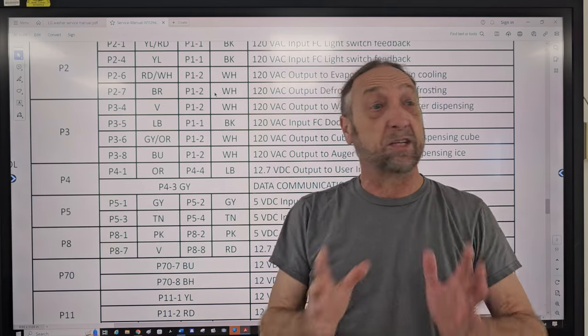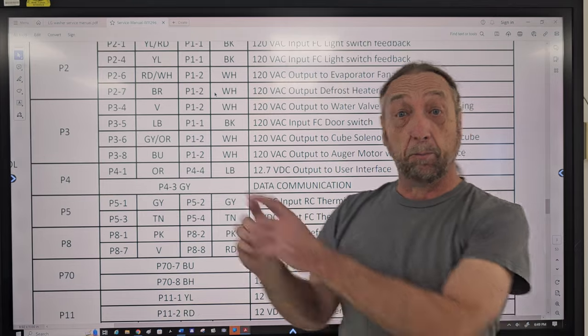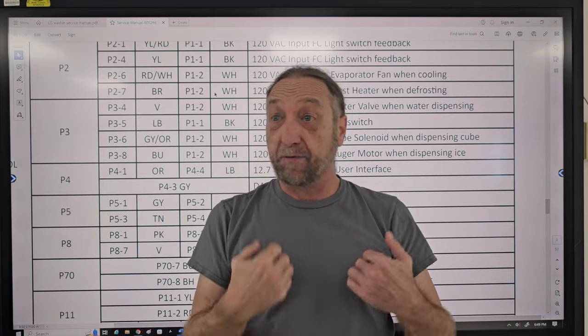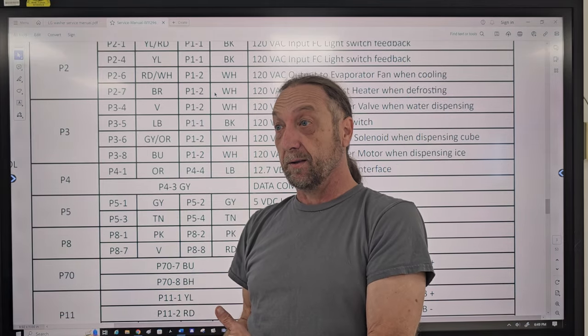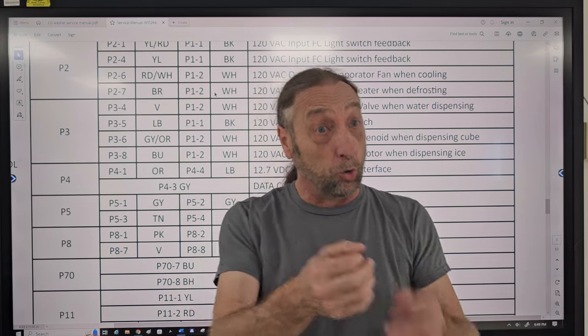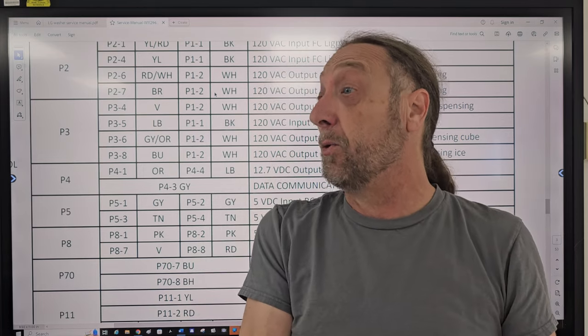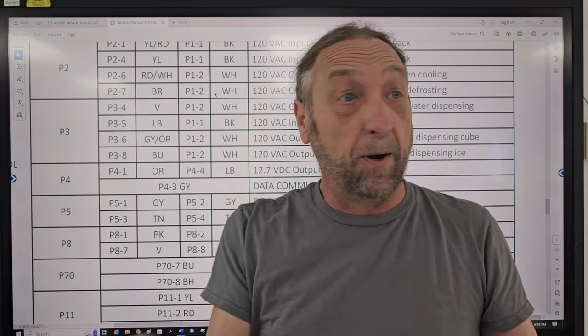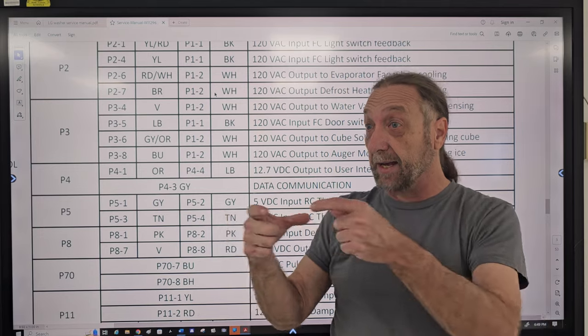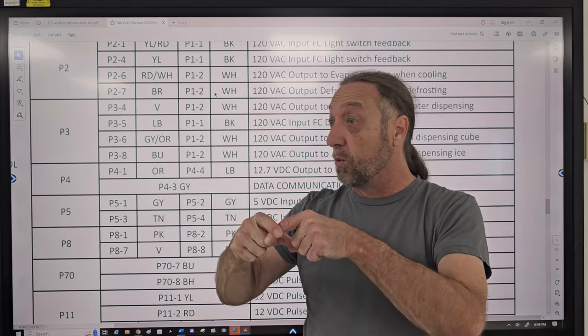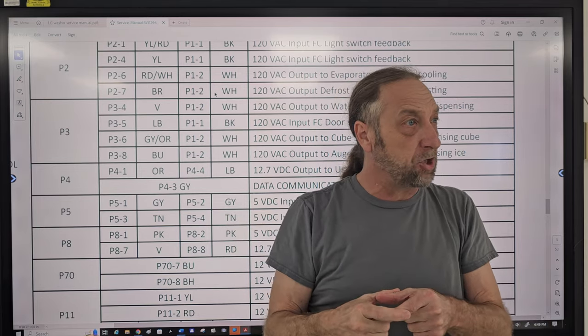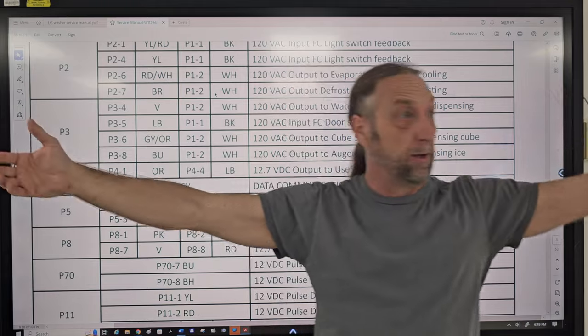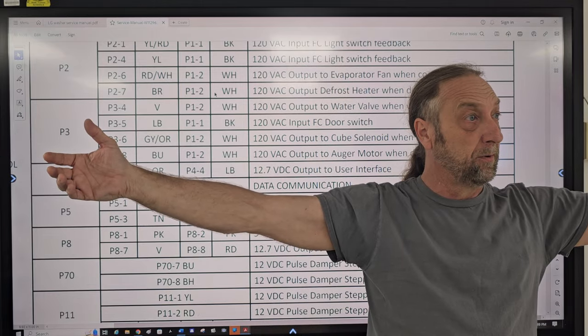That voltage test is only telling me, hey, the board's sending power. I physically see the fan's not running. Now, the next step would be to go to the fan and say, do I have the power there? Remember I talked about the stove the other day, the guy had a quick disconnect and the neutral wire was not making connection, and that was between the board and the components, okay?